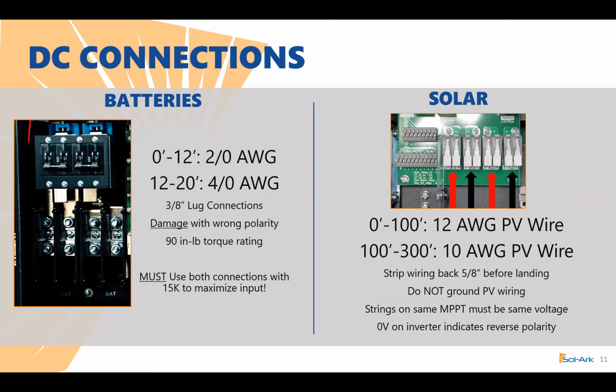Sorry, 2-aught and 4-aught, my apologies there. We'll be using 4-aught wiring and make sure that we can meet the maximum current and make sure that there's not too much voltage drop. The more voltage drop you have in a battery bank, the more capacity you're missing out from it. So we don't want that to happen. They're about 3/8 of an inch for lug connections. The only time you'll ever hurt it is if you do the wrong polarity. So please do not. They're very clearly labeled positive and negative. And then when adjusting your battery termination onto that terminal, it's going to take about 90 inch-pounds of torque rating.